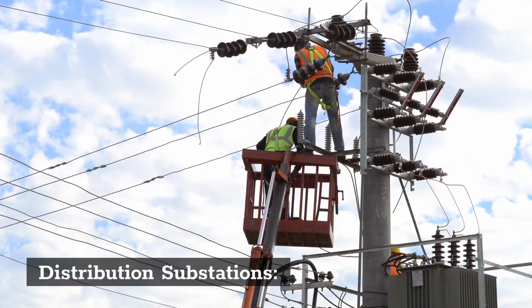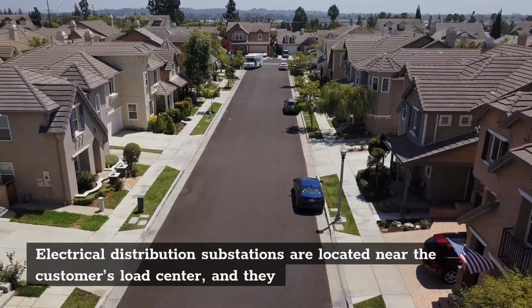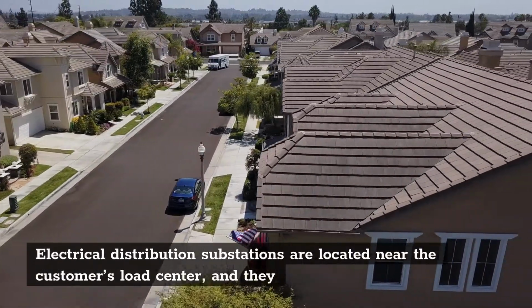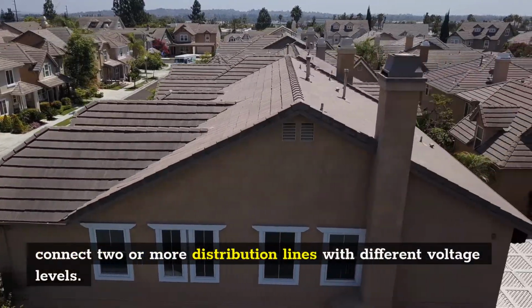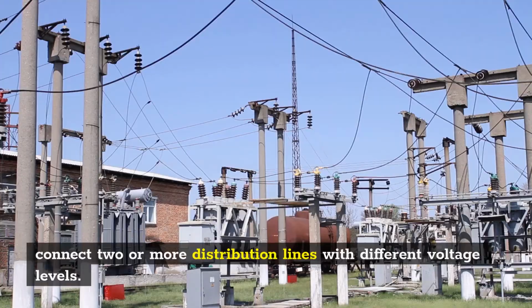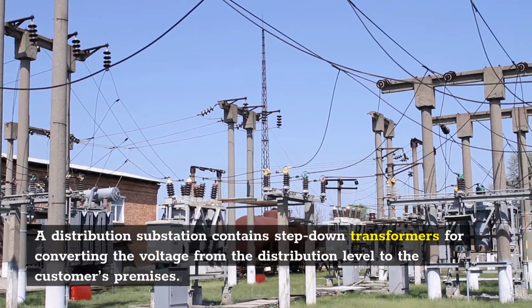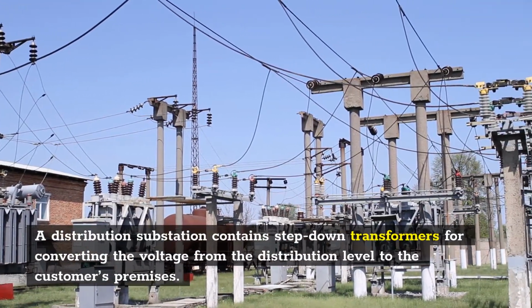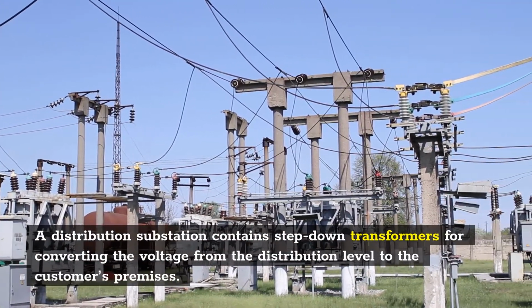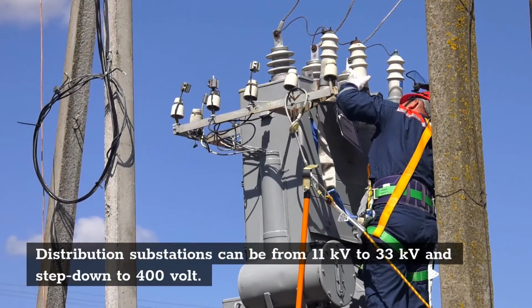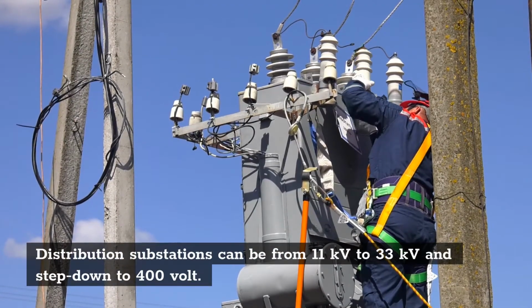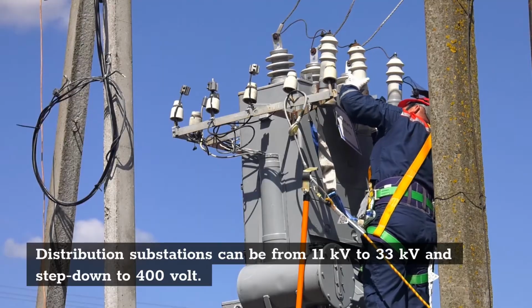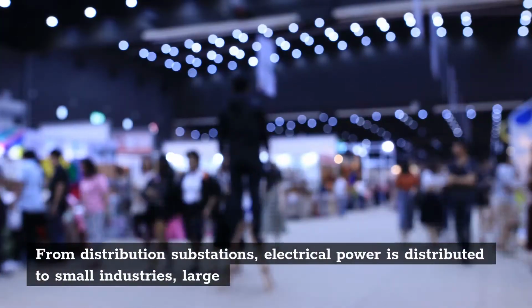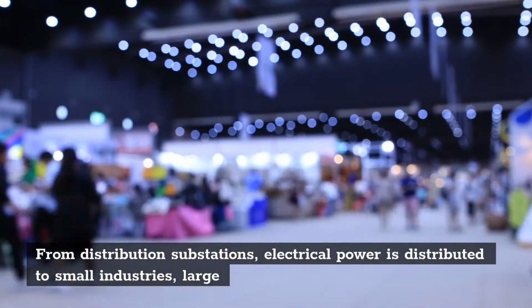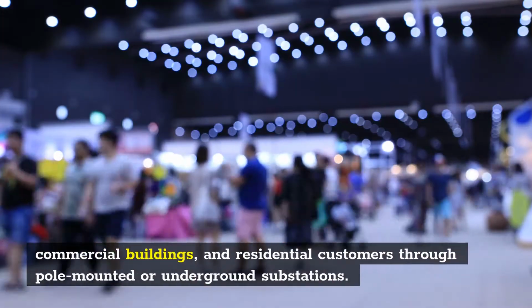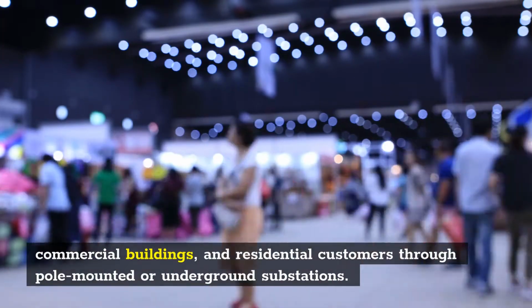Distribution substations. Electrical distribution substations are located near the customer's load center, and they connect two or more distribution lines with different voltage levels. A distribution substation contains step-down transformers for converting the voltage from the distribution level to the customer's premises. Distribution substations can be from 11 kV to 33 kV and step down to 400 V. From distribution substations, electrical power is distributed to small industries, large commercial buildings, and residential customers through pole-mounted or underground substations.